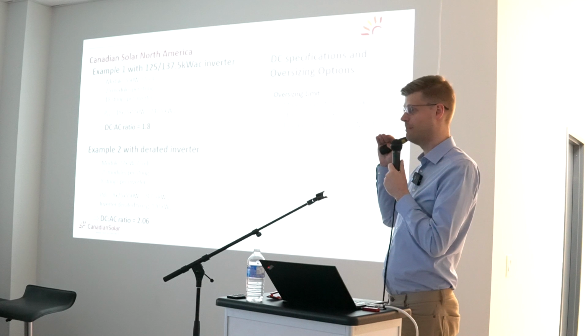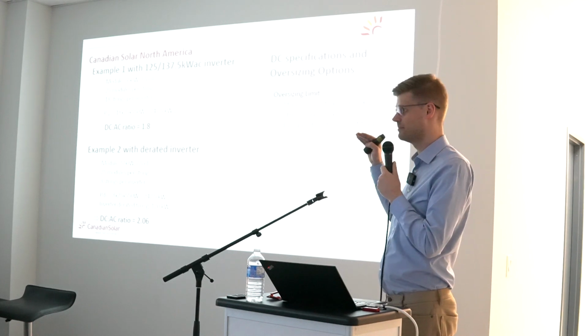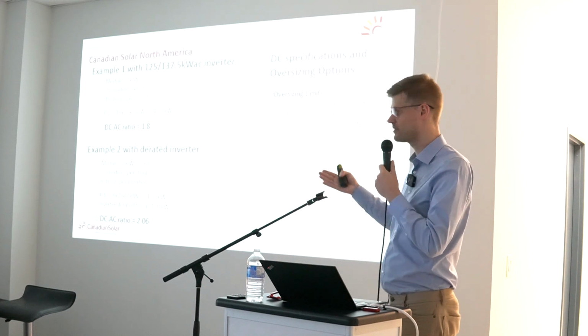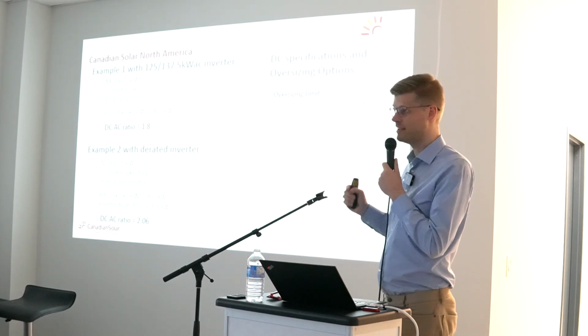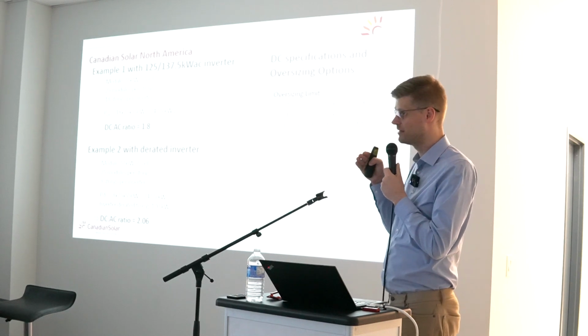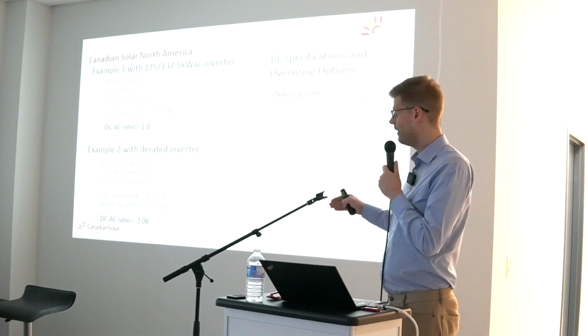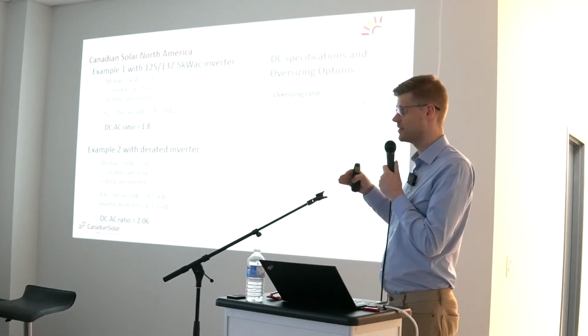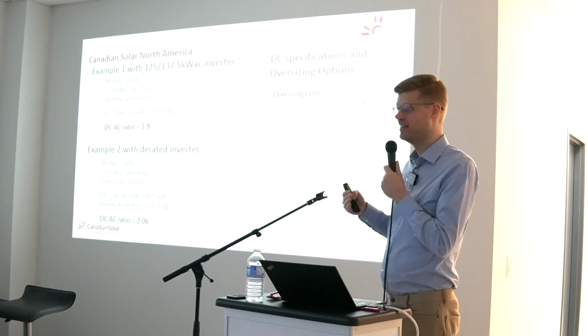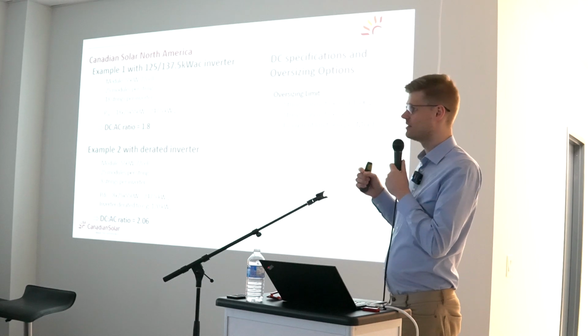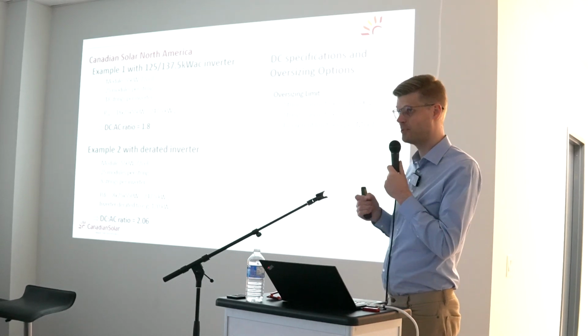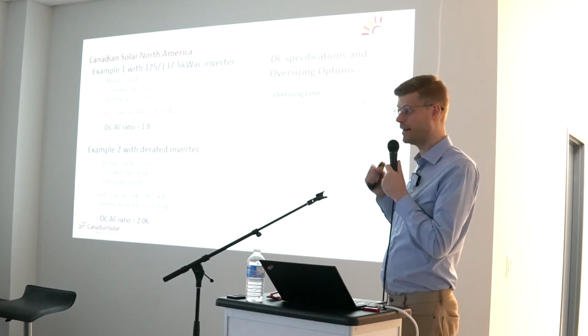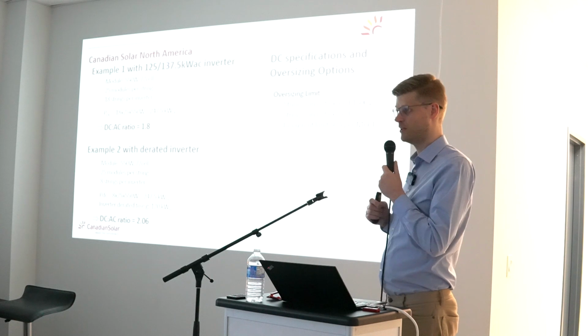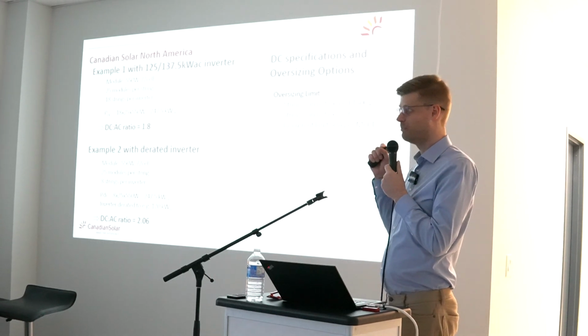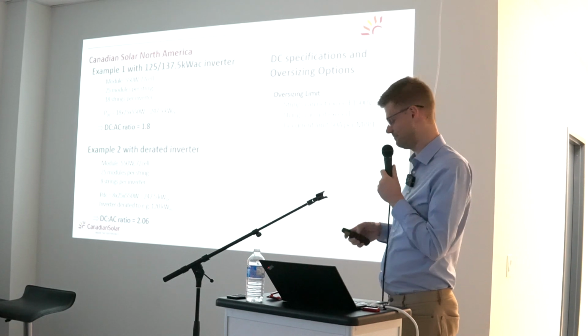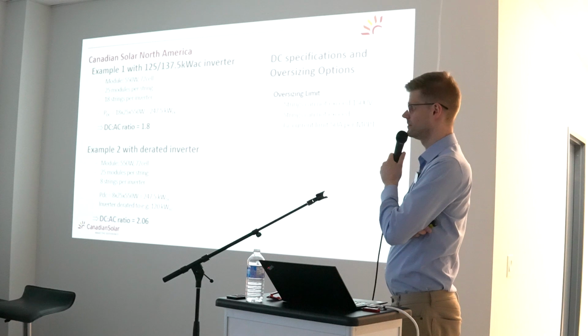So the question now is, how do you get the most AC capacity into a system that you already have or the customer already provides, in our case, 400 amps, 600 volts. And the derating can be used to dial the inverter exactly to the point where you max out your service without changing it. And then the oversizing can be used to optimize your system so that you still get a lot of solar power on your roof. So, to sum that up, it's not only the most efficient system from a technical perspective, it's the most efficient system from a financial perspective. Because if a customer puts 500 kilowatts on a roof, they like the environment, but they like the monetary savings the most, typically. If I can add to that, a lot of times you have contract capacity.